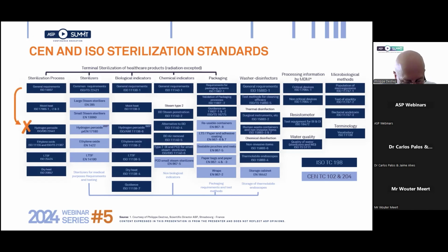ISO 22441 will replace ISO 14937 as the reference norm for H2O2. This doesn't mean that ISO 14937 will disappear from this picture. It will still continue to be used for all sterilization modalities which do not have a dedicated norm. Click, please. Like for steam and EO, ISO 22441 will later be completed by a BI ISO standard, which will be called 11138-6, and by an equipment standard mainly intended for sterilizer manufacturers. The name of that standard is EN 17180.